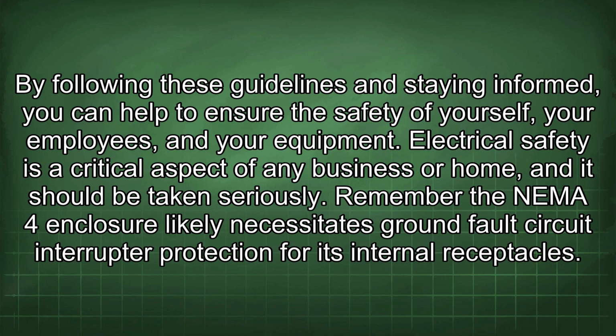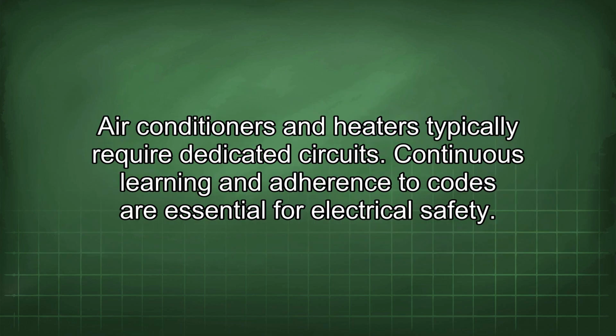Remember, the NEMA 4 enclosure likely necessitates ground fault circuit interrupter protection for its internal receptacles. Air conditioners and heaters typically require dedicated circuits. Continuous learning and adherence to codes are essential for electrical safety.